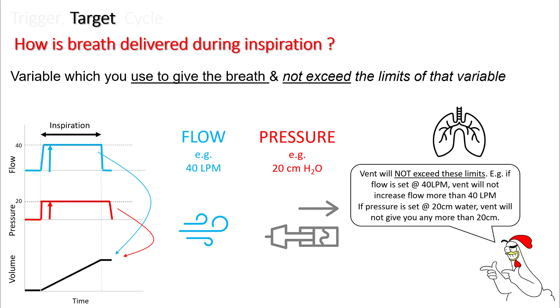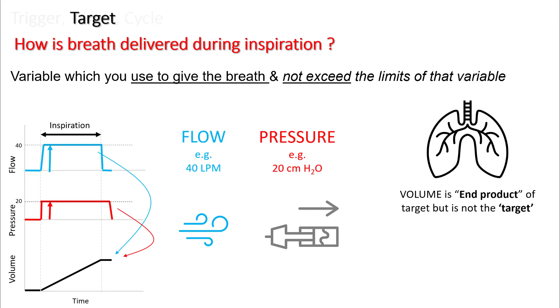That means if you set your flow at 40, the vent will not increase the flow more than 40 liters per minute. And if the pressure is 20, the vent will not give you any more than 20 centimeters. And both of these will generate volume. So volume is the end product of this target, but it is not the target. So you can either set a pressure target or a flow target. And this target will continue till the cycling phase starts.